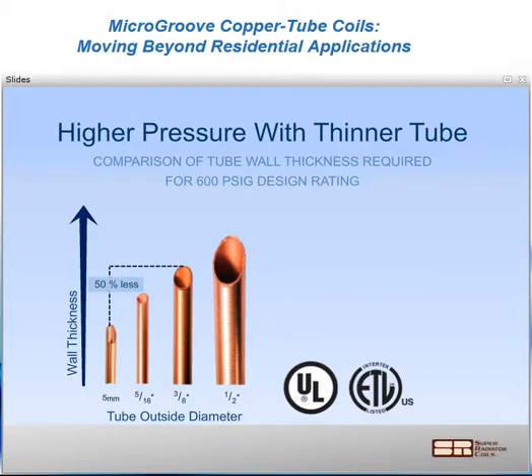Another interesting attribute, in addition to the heat transfer performance attributes, is that the material strength benefits are unique as we move into smaller and smaller diameter tubing. What you see here is actual values shown in a relative comparison of 4 different copper tube diameters, 5 millimeter on up through 1/2 inch, and the wall thickness that would be required to meet a 600 PSIG rating. The material properties and the hoop stresses are in our favor: 50% less wall is required to achieve those same strength ratings. Now, you may not choose to design in that fashion, but again, it is in your favor, and it gives much more flexibility of choice in design to reach those high pressures. When might you do that? Again, higher pressure refrigerants, 410A, CO2 applications. We're finding that MicroGroove 5 millimeter is an excellent fit for challenges with higher pressures.